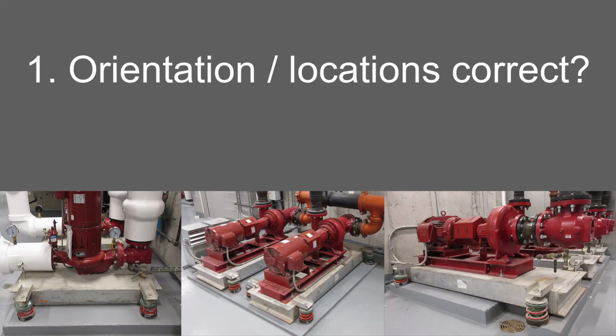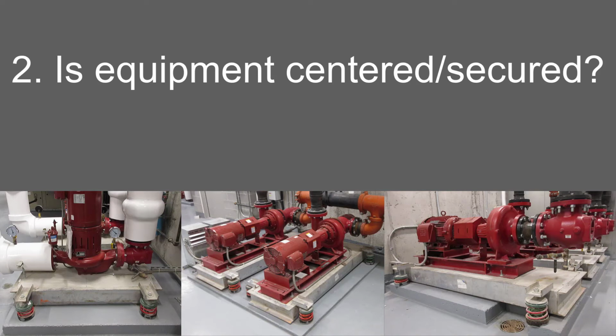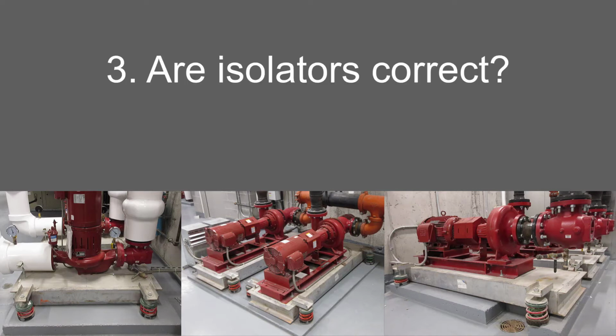So let's move on to our first item. Are the inertia bases filled with concrete with the correct pumps and in the correct orientation? Yes, all 3 have concrete, are used with the right pumps, and are oriented correctly, right side up, and aligned with the equipment. Is the equipment centered and secured correctly? Yes, all pumps are lined up on the center lines of the bases and are secured to their bases. Are the correct isolators in the correct locations? Yes, as we mentioned during the videos, they all have the correct isolators in the correct locations.